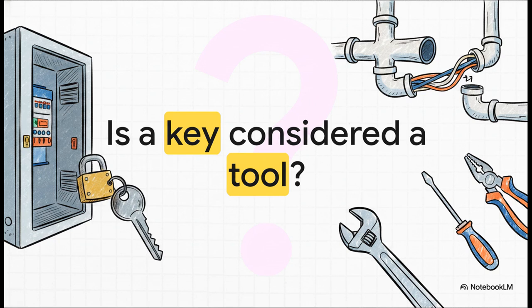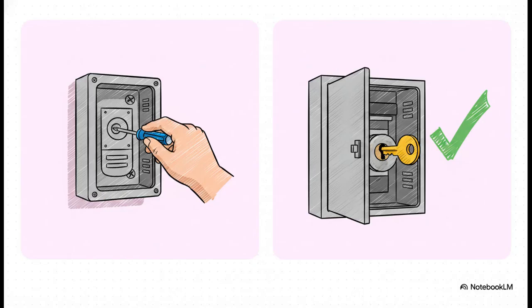Think about a typical day on the job site. Say you have to temporarily shift a plumbing pipe just to reach an electrical wire. Can you still legally call that wire accessible? Or what if a panel board is locked? If you need a key to open it, does that key suddenly count as a tool? Let's dive into this, because rigid semantics absolutely matter in electrical safety. One tiny misunderstood word can literally be the difference between a fully compliant installation and a really dangerous code violation. So, back to that locked panel board scenario.